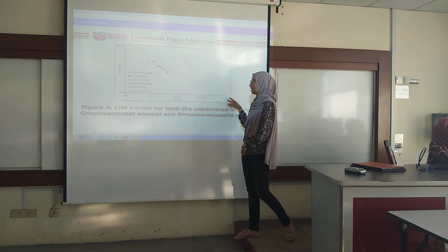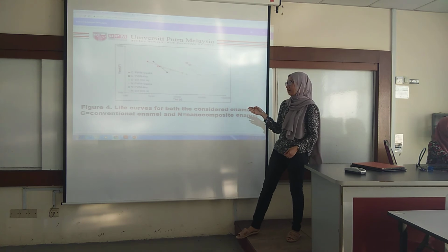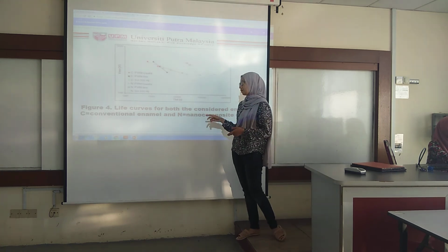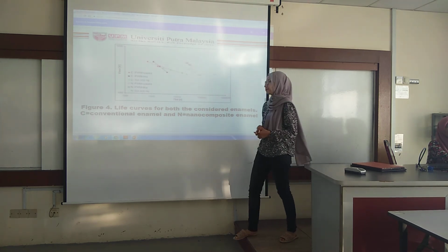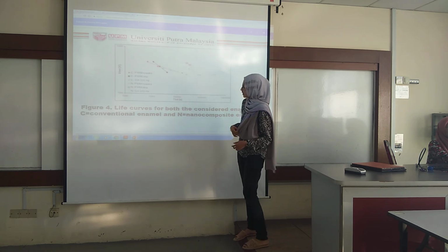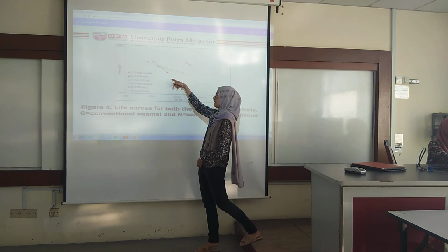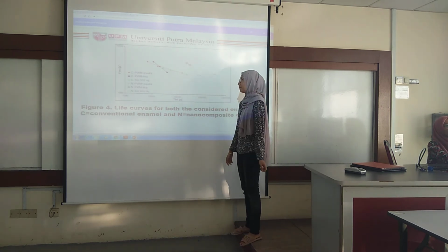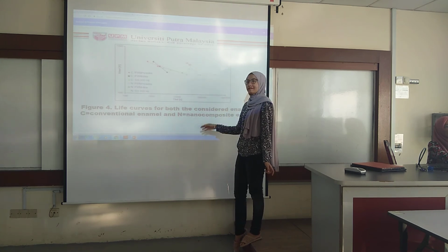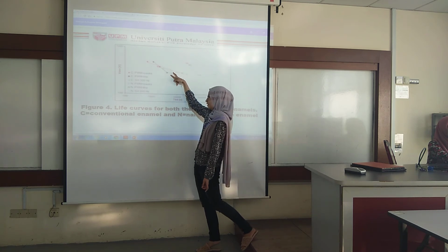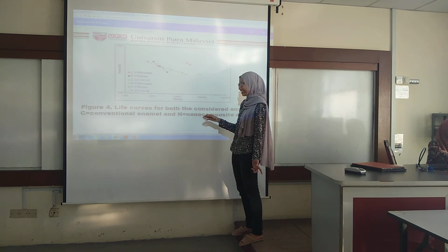This is the life curve figure for both considered enamels. We have two types of enamels, which are conventional enamel and nanocomposite enamel. The black one is PWM applied. When the voltage decreases, the time taken for it to break down increases.